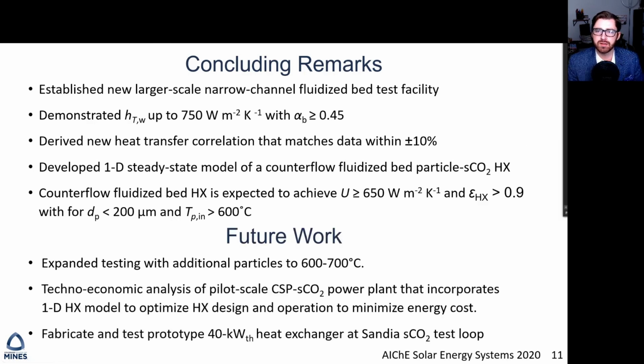Future work includes expanded heat transfer testing with additional particles up to 600 to 700 degrees C, continuing ongoing work developing a techno-economic multivariable optimization model of a pilot-scale plant to select preferred designs and optimization to minimize the levelized cost of electricity. And finally, as a critical next step in validating this approach, fabricating and testing a demonstration 40 kilowatt heat exchanger at Sandia's SCO2 test loop.